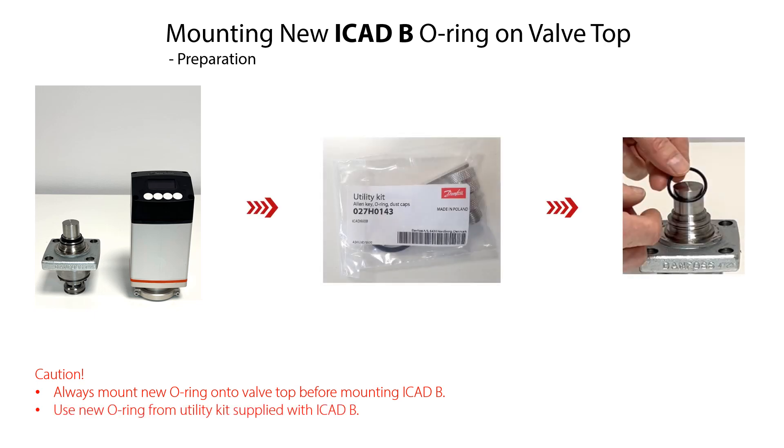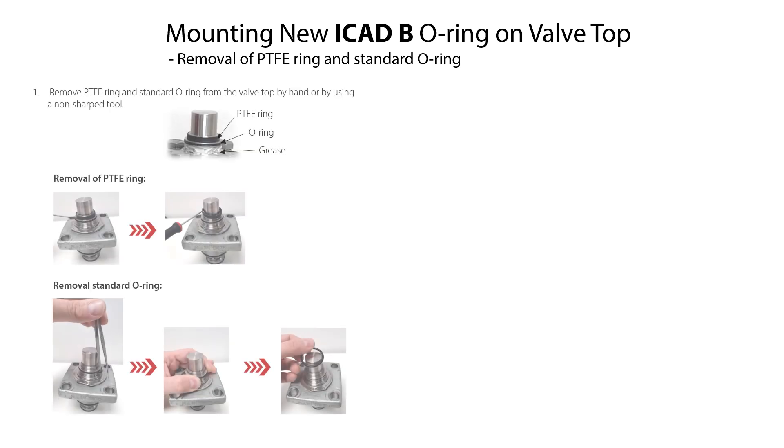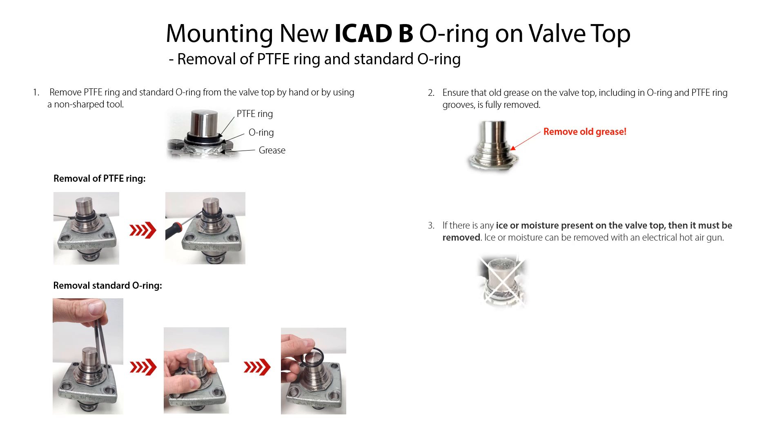This new o-ring is part of the utility kit supplied together with the ICAD B. Do the following as illustrated: if the PTFE ring and standard o-ring are mounted on the valve top, remove these parts by hand or by using a non-sharp tool. Ensure that any old grease on the valve top, including in the o-ring and PTFE ring grooves, is fully removed. If any ice or moisture is present on the valve top, it must be removed using an electrical hot air gun. After removal, ensure that the valve top is totally dry.